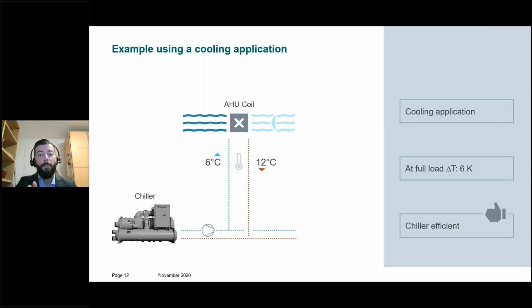The chiller sends cold water to the coil of the air handling unit, and the incoming air in the duct is cooled accordingly. So after transmitting its thermal energy, the water returns slightly warmer, right? The system in this case is designed to operate at full load with 6 degrees flow temperature and 12 degrees return. So we have a difference of 6 degrees, and this is what we call DeltaT. This difference is very important because a chiller works most efficiently when this gap is the largest. So what you want to do is to keep the DeltaT at the highest possible level.